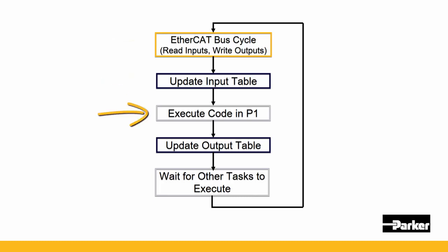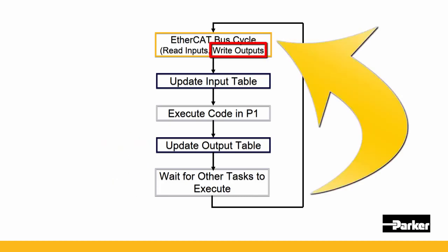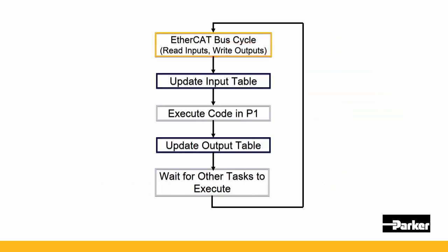With the latest input values, it'll now execute the logic found in P1. Lastly, it updates the output table based upon the changes that logic dictated by P1. Note, the outputs are actually not written to the slaves until the next EtherCAT bus cycle.